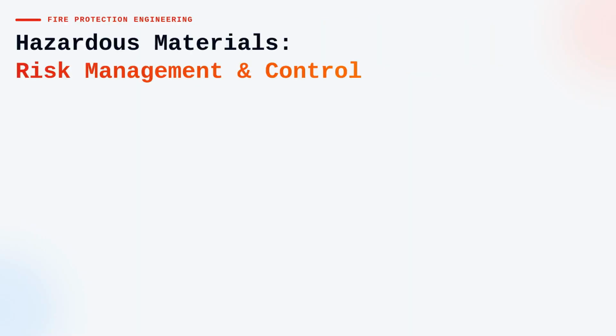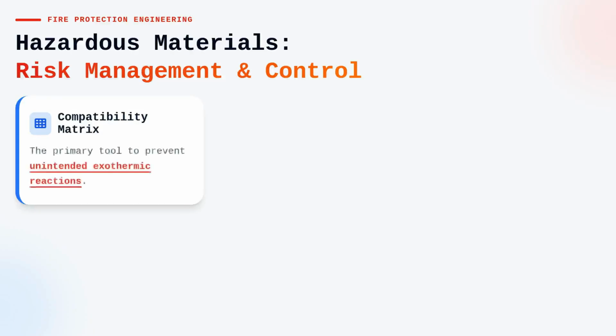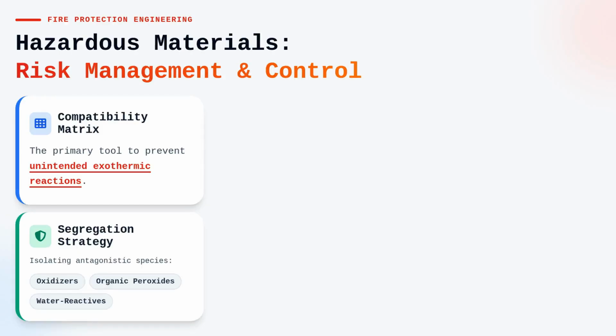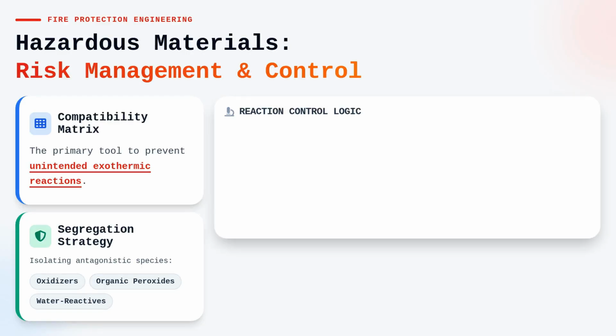In the professional practice of fire protection engineering, hazardous materials represent a distinct category of risk that transcends traditional fuel load calculations. We must begin by conceptualizing the chemical compatibility matrix, which is the foundational tool for preventing unintended exothermic reactions between disparate substances. When dealing with oxidizers, organic peroxides, or water-reactive materials, the primary objective is the segregation of chemically antagonistic species. A common failure in industrial facility design is the assumption that proximity is merely a logistical concern, rather than a critical reaction kinetics issue.